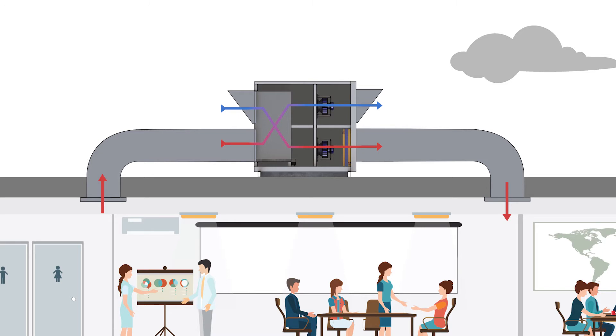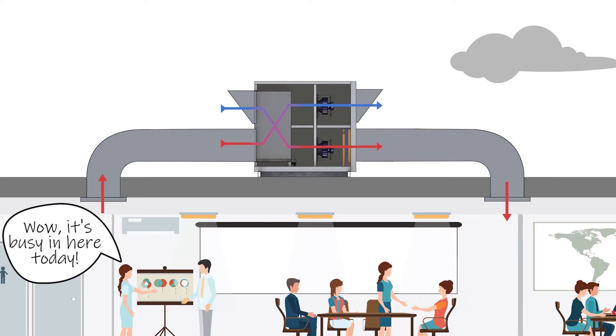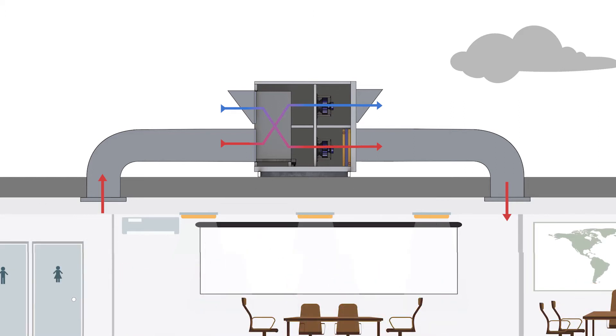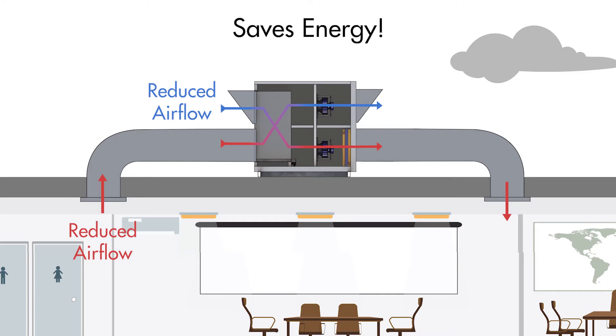For example, let's say you have an indoor space that nominally has large occupancy levels. This means that large amounts of fresh air ventilation will be required, and using an ERV or HRV unit will be beneficial. But what if there are extended amounts of time where few people occupy the space? Then turning down the outside air volume to meet the current ventilation demand will save energy.